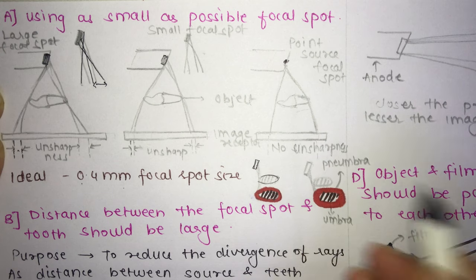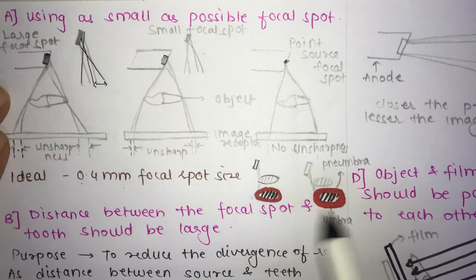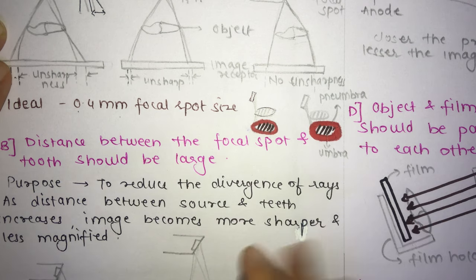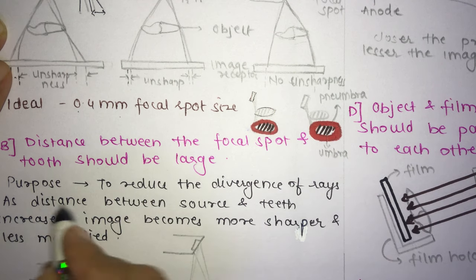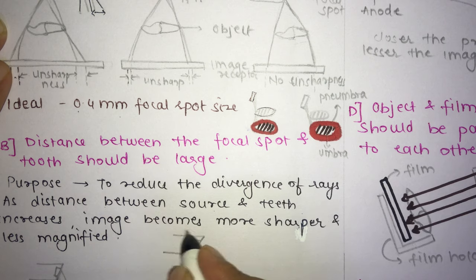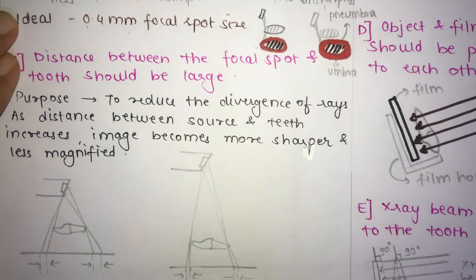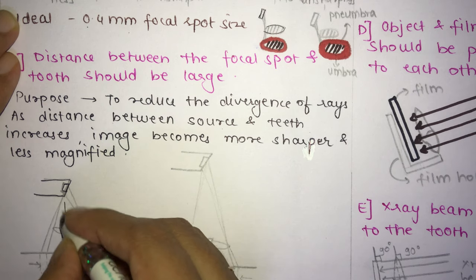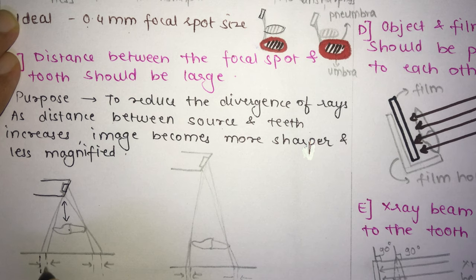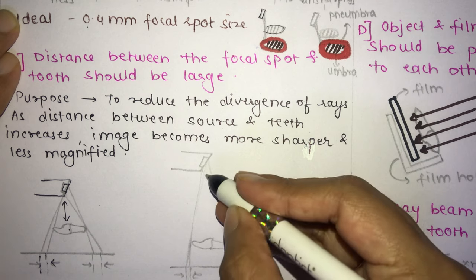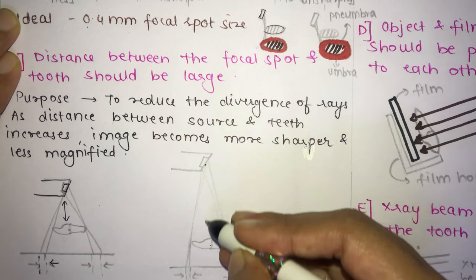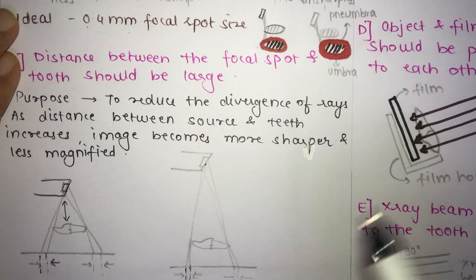The second principle is that the distance between the focal spot and the tooth should be large. The purpose is to reduce the divergence of the rays. As the source-to-tooth distance increases, the image becomes sharper and less magnified. When this distance is small, there is more unsharpness and the image is more magnified; when it is larger, there is less unsharpness because the rays are less divergent.